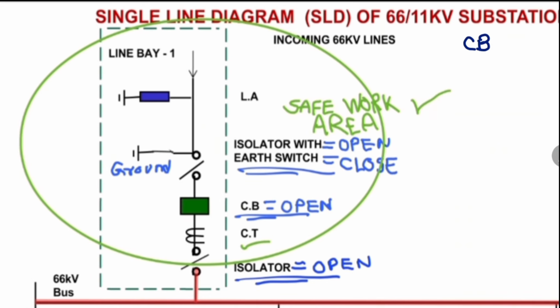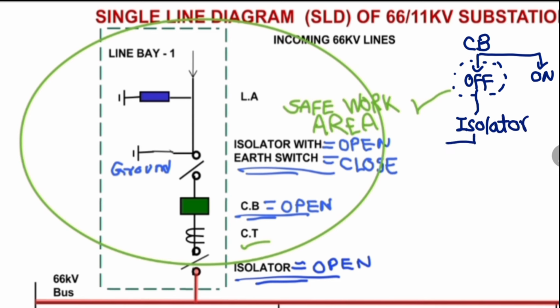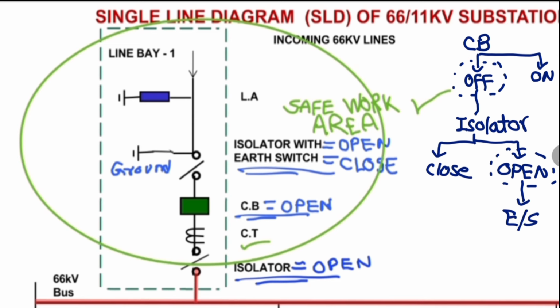The circuit breaker can be off or on. When the circuit breaker is off, only then can the isolator be operated, that is, the isolator can be made to close or open. When the isolator is open, only then can the earth switches be operated, that is, earth switches can be made to close or open.